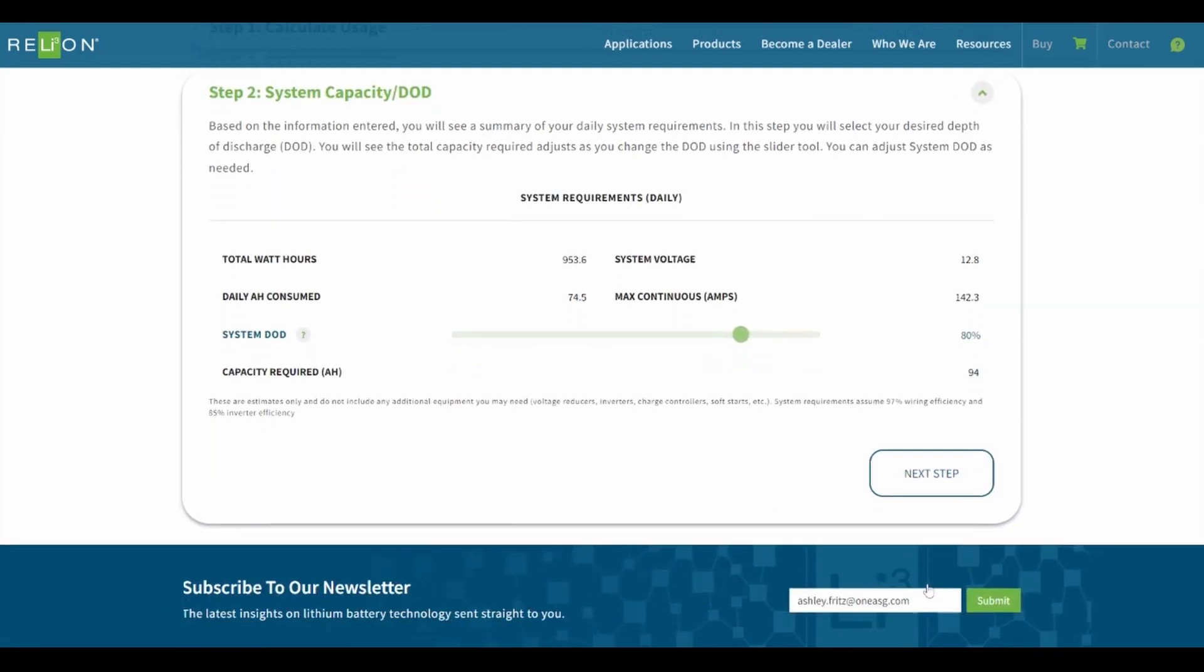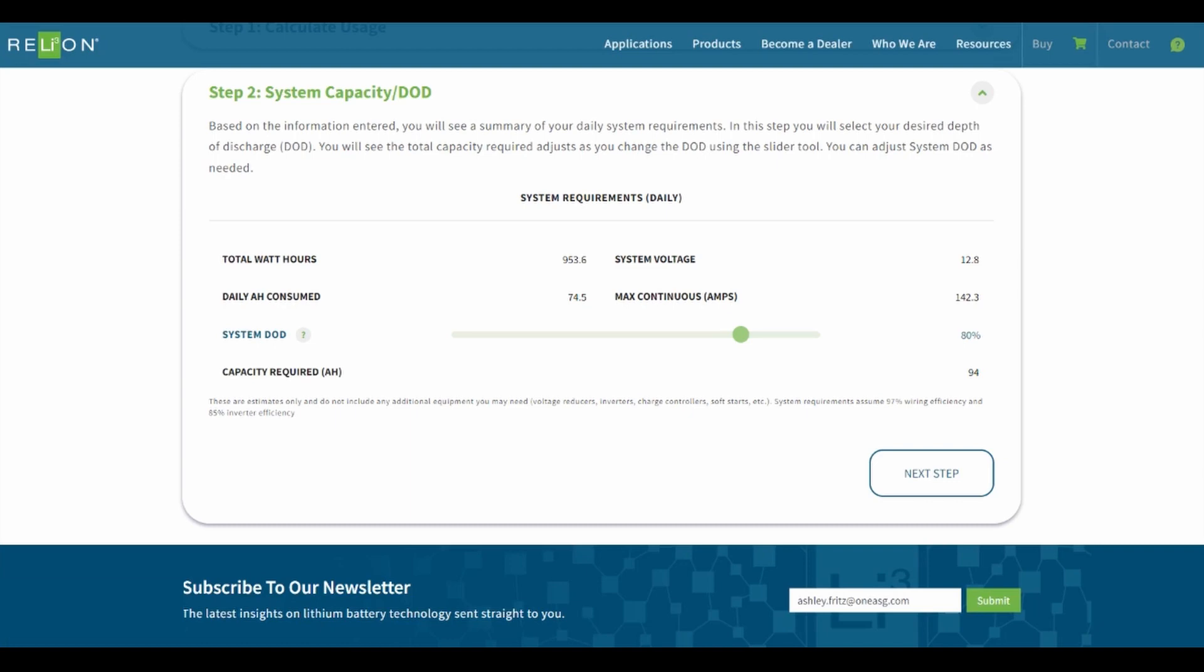Step 2. Based on the information entered, this step will show a summary of your daily system requirements. Here, you may select your desired depth of discharge. We recommend discharging be limited to 80-90% to avoid the battery management system disconnecting the battery. Click Next Step.